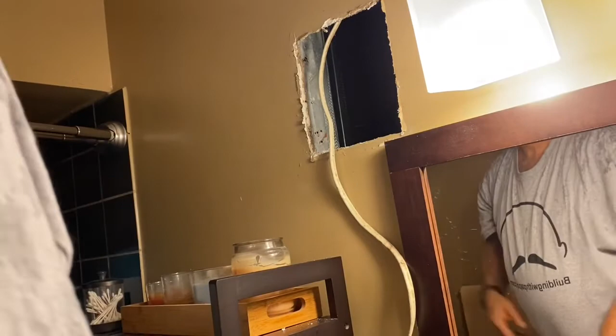Good, so now I can see up in there that I have a chase next to this duct. I'm going to cut a hole in it, go in the attic, and pass down a duct that I'm going to attach to the new fan. I'm going to cut a hole in that drywall that goes to the attic and bring the duct down from there to attach to the fan.